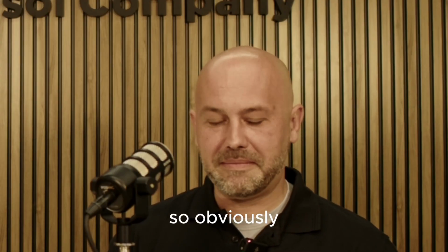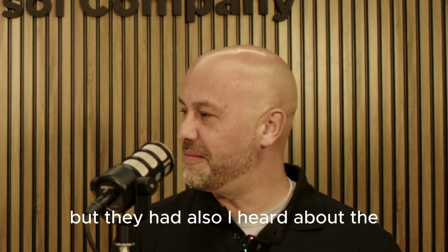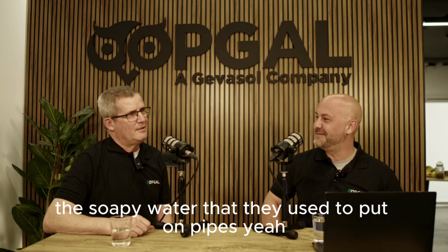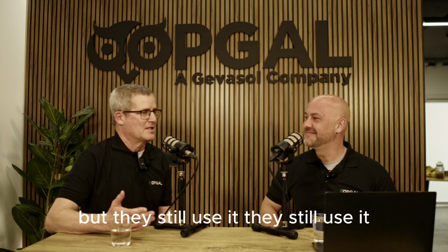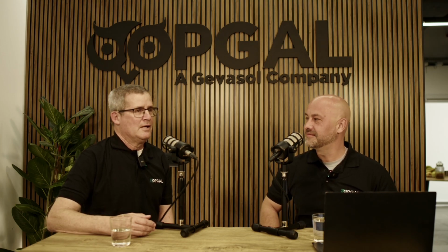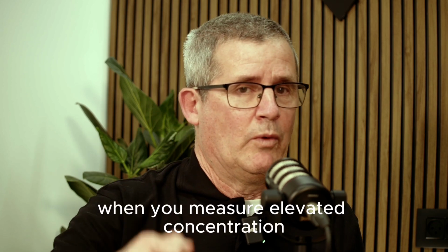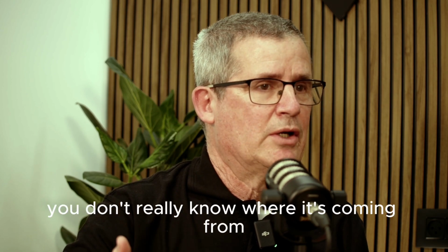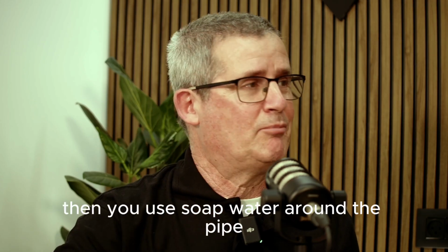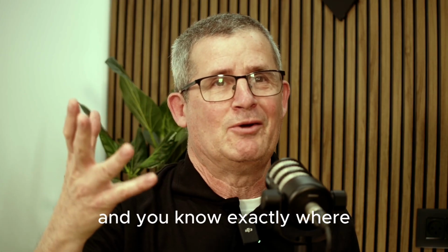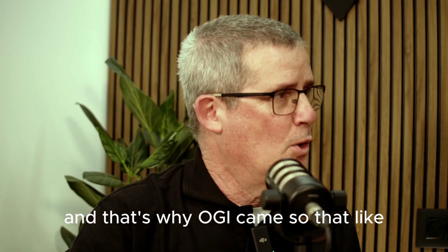So obviously, the canary story is very sad, though. But I also heard about the soapy water that they used to put on pipes. Yeah, this is operational. This is not a regulatory method, but they still use it. Sometimes when you use the old sniffer idea and you measure elevated concentration, you don't really know where it's coming from. Then you use soap water around the pipe and you see where the bubbles come out and you know exactly where it is. But this is a really primitive method, and that's why OGI came.